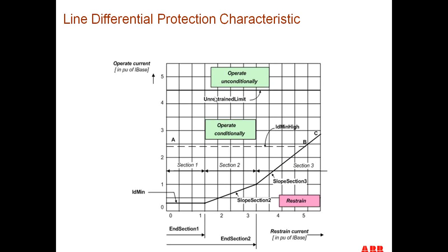We also have what's called the unrestrained limit. This limit on modern relays dates back even to the less protected relay. We would have an element that, no matter how high the restraint current was, if the operate current got up to this level, it would operate, period, regardless of what the level of restraint current is. So that's what this unrestrained limit is.